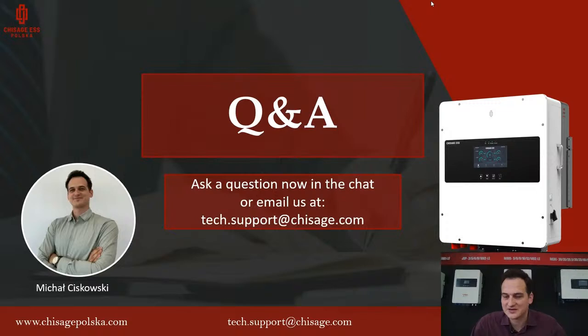I will just say more about this load, because I see a lot of questions about it. For the backup load, we can put all the power of the inverter. So for Mars 10 we can put 10, but if we have one phase load more than 5 kilowatts, the inverter will just give 5 kilowatts for this phase. So maximum 5 kilowatts per phase, and all the phases have to sum up to the rated power of the inverter.